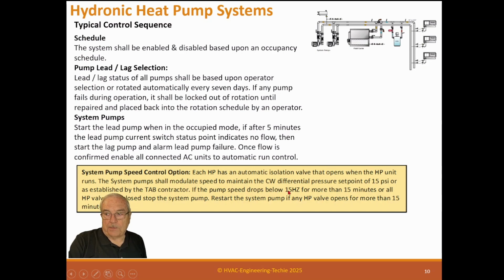If the pump speed drops below 15 hertz or maybe 12 hertz for more than 15 minutes or all heat pump valves are closed, stop the system pump. Reset the system pump if any heat pump valve opens for more than 15 minutes. So this allows this system to run the central plant, but also it runs at variable speed.